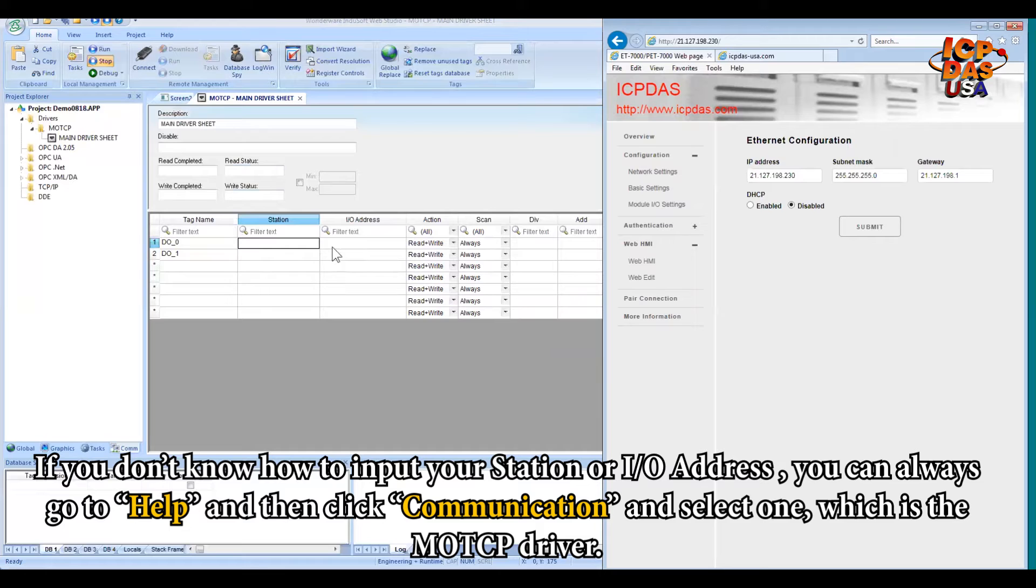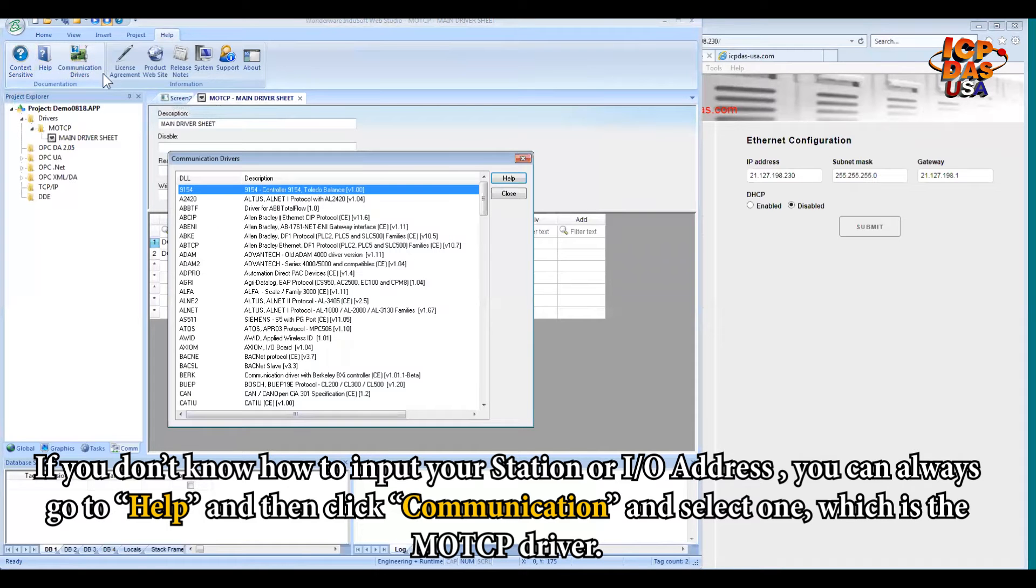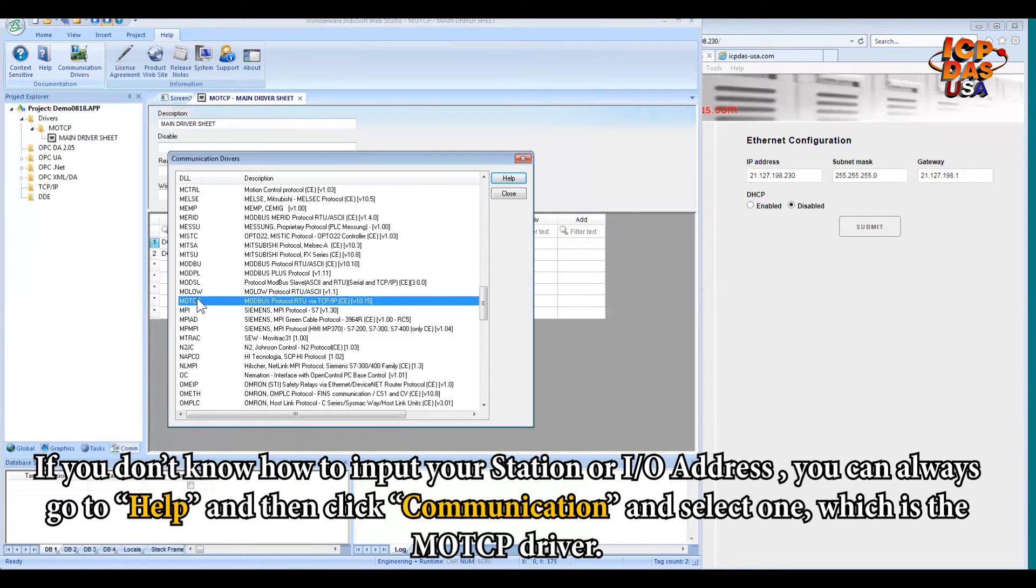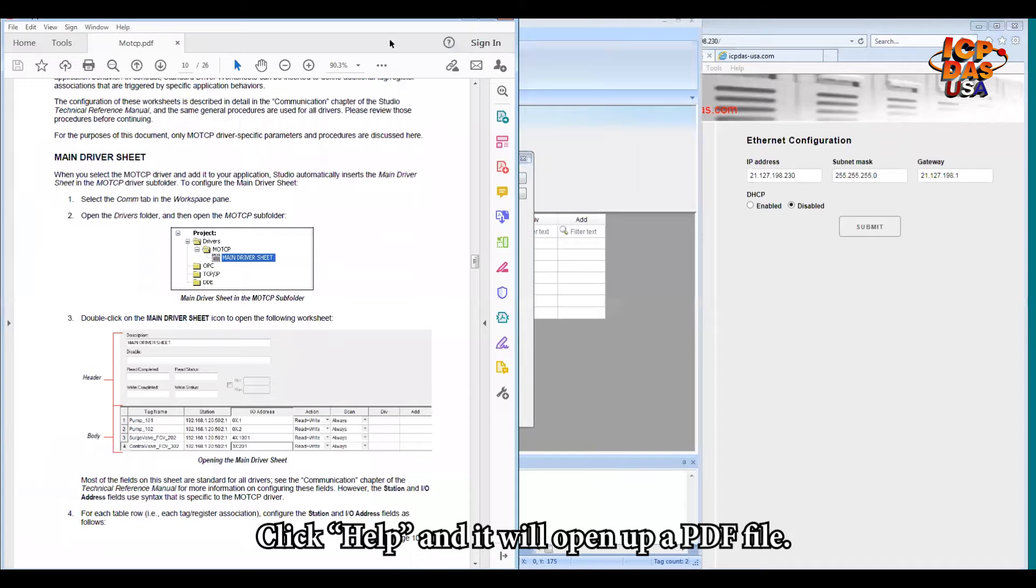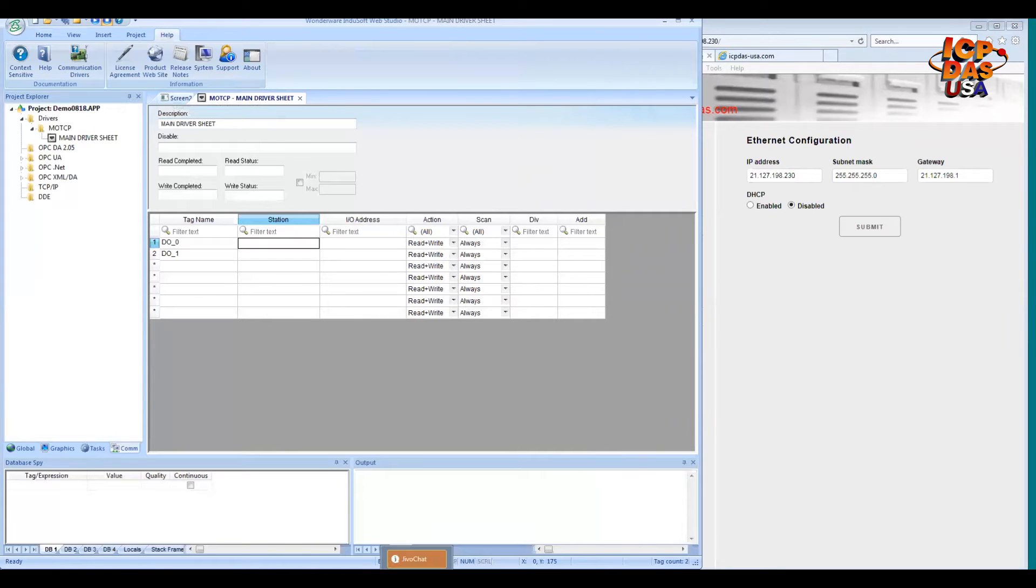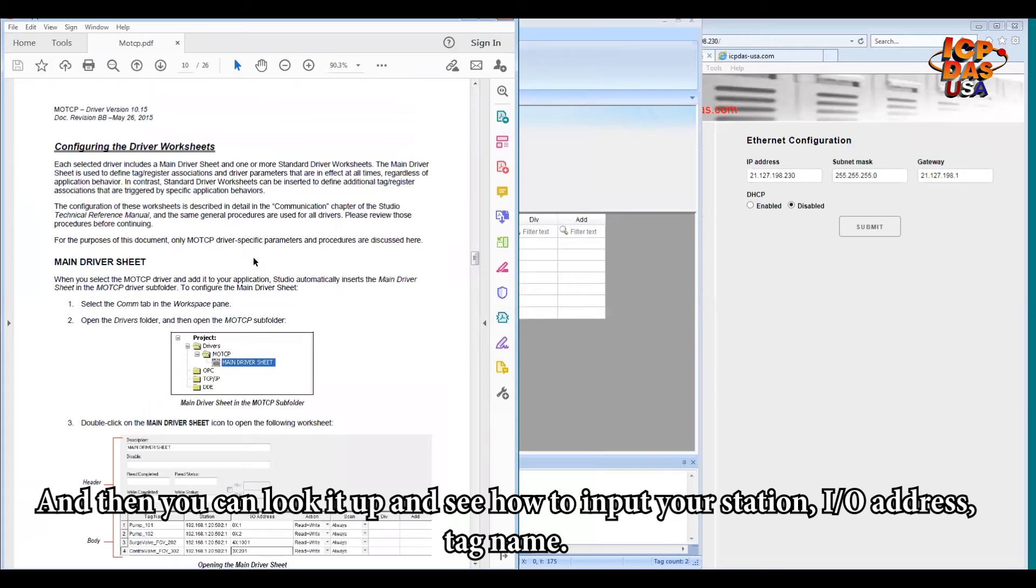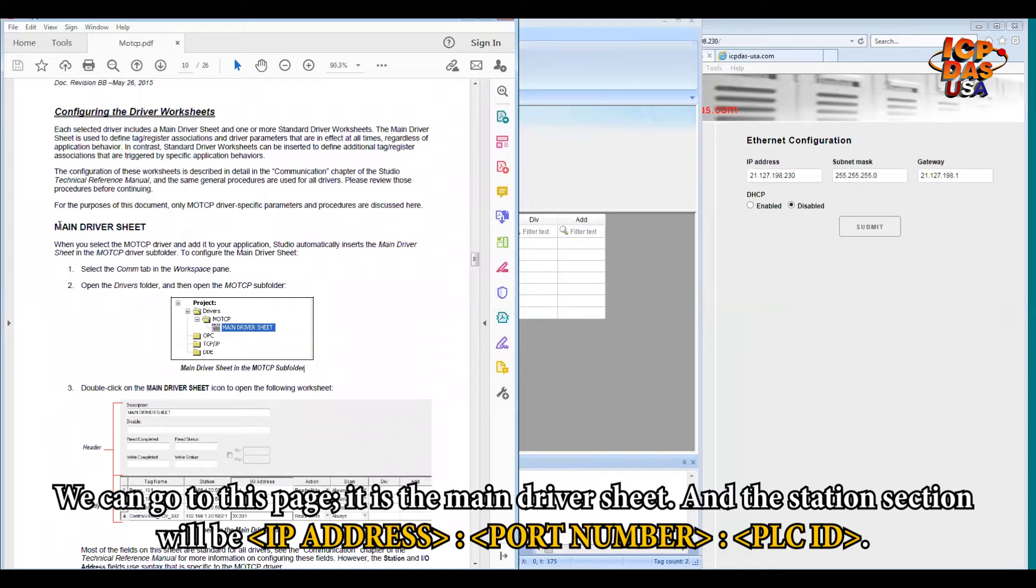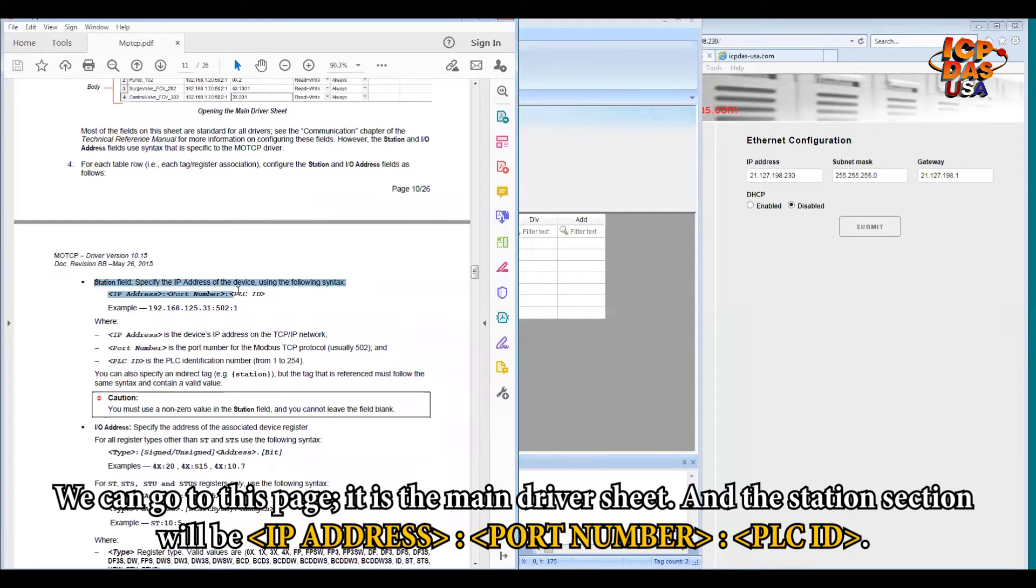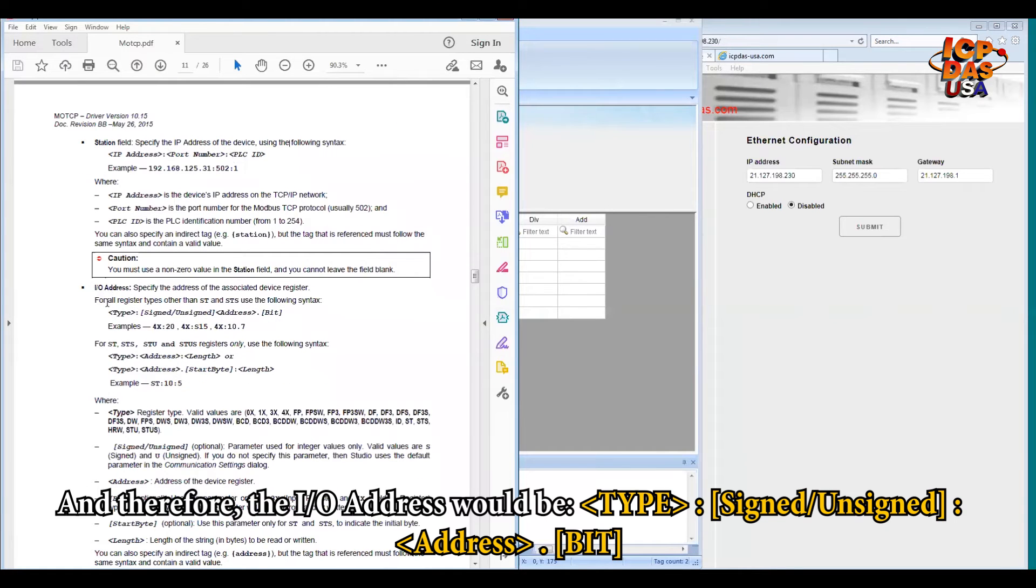So if you don't know how to input your station or I/O address, you can always go to help and then click communication driver. Select the one which is the MOTCP driver. Click help. It will open up a PDF file. So like this. And then you can look it up and see how to input your station, I/O address, tag name. So we can go to this page. It's the main driver sheet. And the station section will be my IP address, colon, port number, colon, PLC ID. And for the I/O address would be the type, colon, and the address itself.